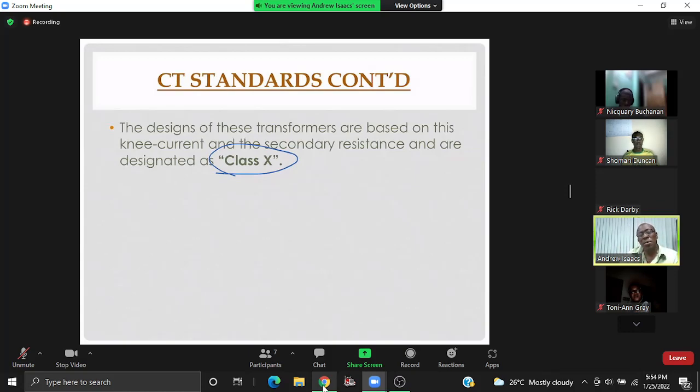the maximum flux occurs on first swing, because thereafter it's in the exponential envelope. So at 90 degrees, this occurs. And so we have an expression now for your current. And we make some assumptions regarding the excitation current. Then you touch back a little on what you would have learned in magnetics, where we have that the flux is a function of the voltage. We do that integral.